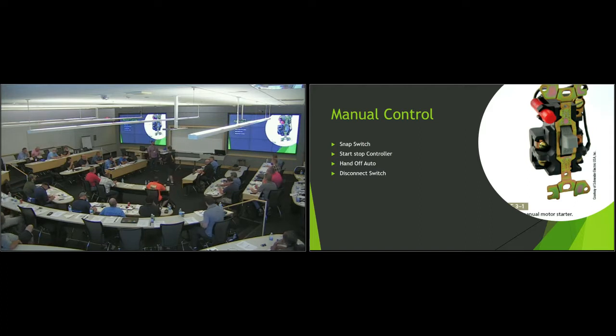Safety is one of the most important parts of our trade. When you're doing controls, just because it might be 24 volts doesn't mean we don't have 120 or 480 coming into the same cabinet. Even though you turn off that disconnect switch, you could still have 120 in that cabinet—you just don't know where it's coming from. There have been electricians who assumed that turning off the disconnect meant everything was dead. Never assume it's dead.